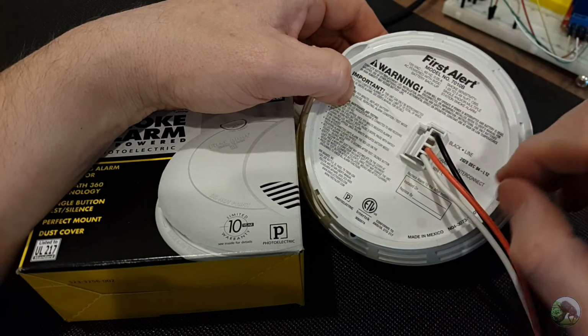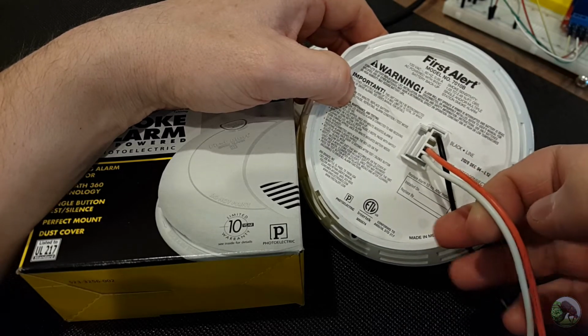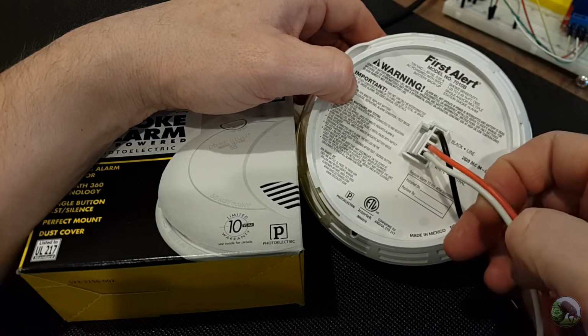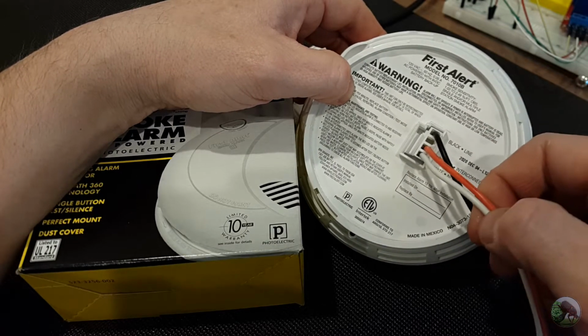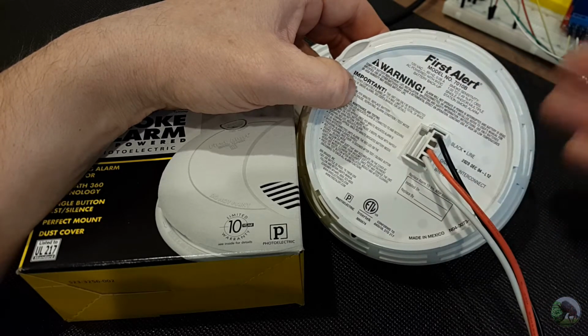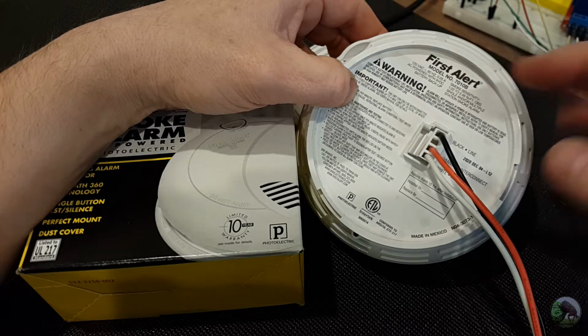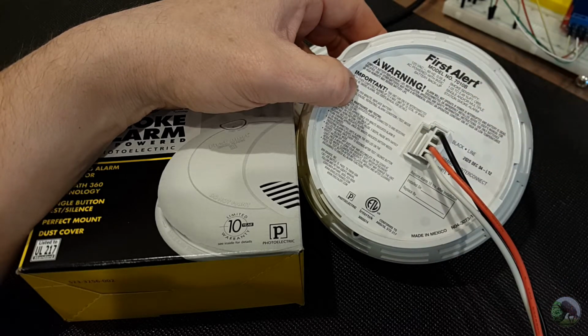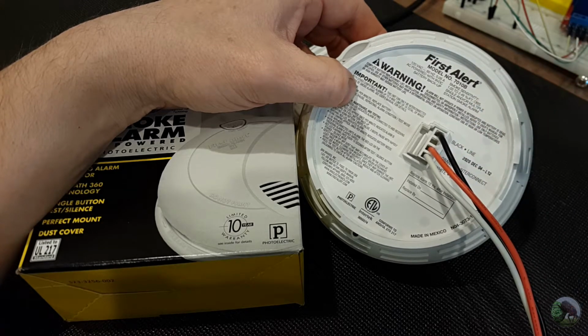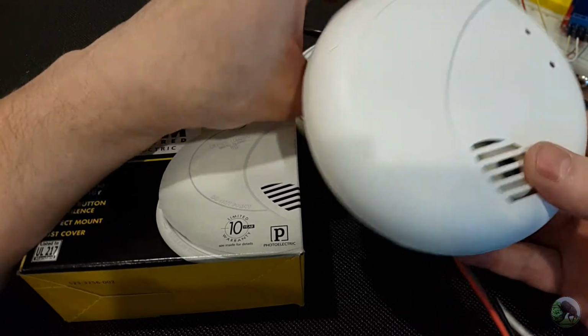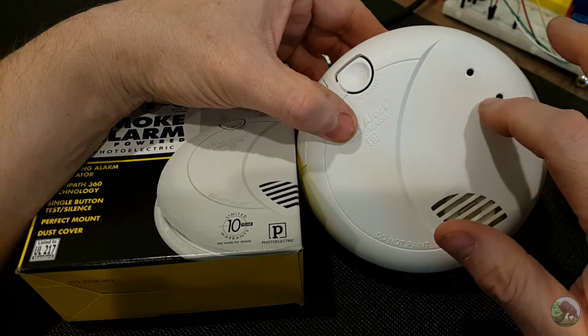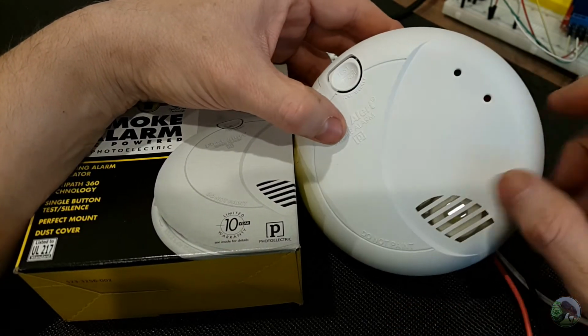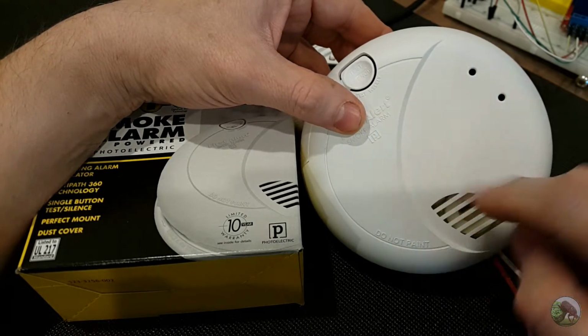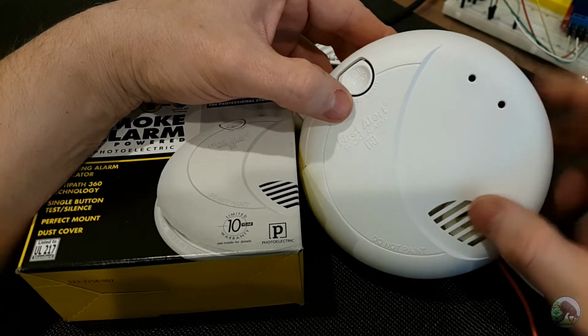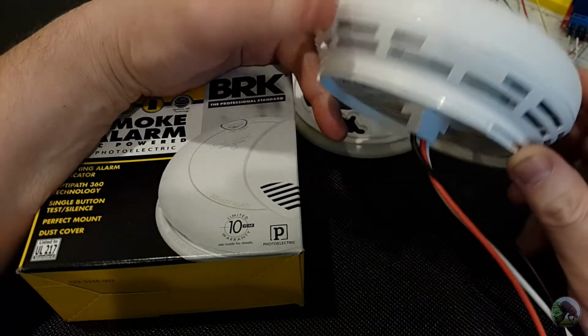The idea there is that all of the smoke detectors in your house actually share these two wires, so that the other smoke detectors will be listening for that 9-volt DC signal, and when they see it, they too will trigger. So all the smoke detectors in your house go off at the same time. The example is if you're sleeping upstairs and in the basement a fire starts, the smoke detector near your bedroom will go off and you'll get up and go investigate to find out where the fire is. And I think most smoke detectors have some type of LED lighting code to indicate which smoke detector was the origin of the alert. So you could walk around your house looking at each of the smoke detectors and know, oh, it was the one in the basement that triggered this alert.